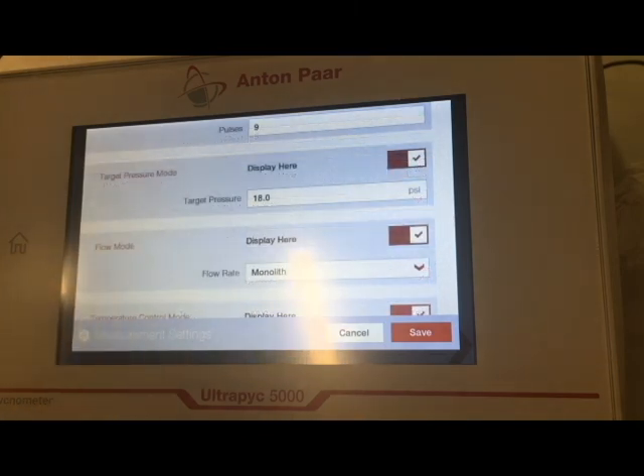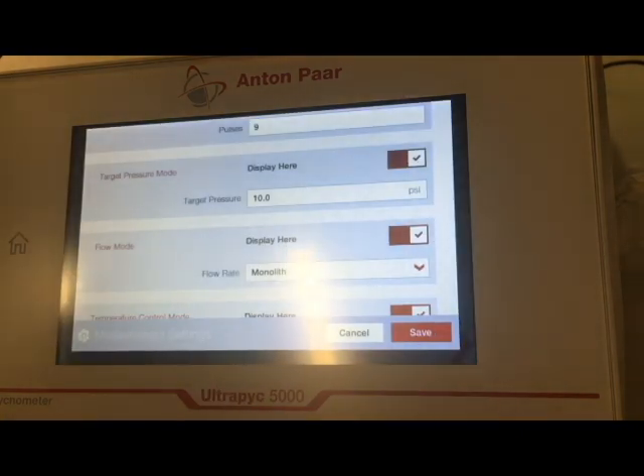Target pressure mode. This is the pressure of helium that's going to be in the system during the test. We can range anywhere from 2 to 20 psi. For a solid sample, also called a monolith, you would want it to be around 18 psi. For a powder, or for the micro, meso, or nano cells, you want it to be 10 psi, which is true for ours. And for a very brittle sample, or for biological samples, you would want to put 4 psi. For the micro, meso, or nano, you can do 10 psi or smaller.